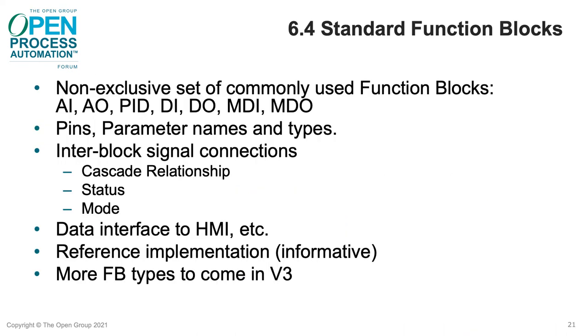Part 6.4 defines a non-exclusive set of commonly used function blocks: analog input and output, proportional integral and derivative block, discrete input and output, and multiple discrete input and output. The standardization of function blocks is done at the interface level — specifically the pins and the parameter names and types, the inter-block signal connections such as the cascade relationship, the status and mode, and the data interface to the HMI or similar applications. We also have a reference implementation, but that is just informative; you aren't required to do it that way.